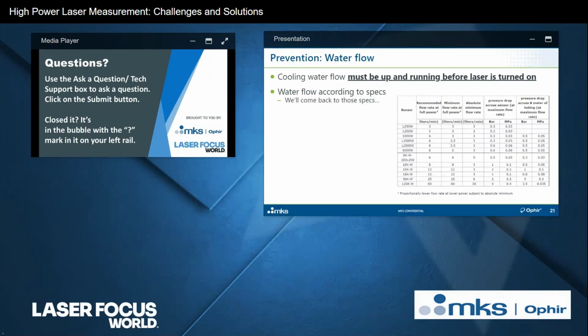So what we absolutely recommend, I was going to say best practice, but it's more than a best practice. It's a highly recommended practice, is that the cooling water flow should be up and running and steady before you turn on your laser. Because again, if you turn on that laser even briefly, and then you immediately press the button to turn on the cooling water, that half a second could easily be enough to have caused the damage already. And the water flow should be according to the specifications of the sensor. We're going to come back to those specifications shortly.